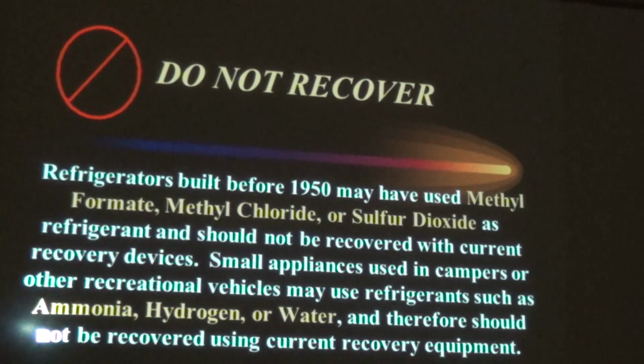So your recovery machine, a black and yellow machine, is made to remove three kinds of refrigerants: Class 1, Class 2, and HFC refrigerants. It's not designed to remove any of those things in the first part of the paragraph, nor is it designed for use on recreational vehicles. Ammonia, hydrogen, and water are the components necessary for chemical absorption air conditioning or refrigeration. So no, we're not doing that either. We're only going to use our recovery machines for CFCs, HCFCs, and HFCs.